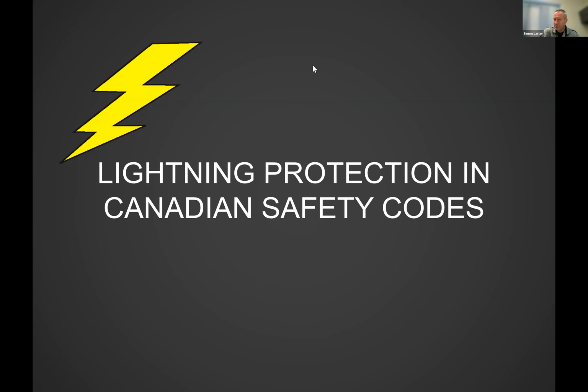The other thing I don't think you will run into very much, though, is from the specific section in B72 on telecommunications equipment protection, and Rogers and Shaw, I think, are both on the CSA B72 committee, and we permit galvanized steel to be used as a grounding conductor in the telecommunications section only. So our main method of stopping theft is concealing the conductor inside a building or in conduit, or even poured into a concrete pour for a reinforced concrete building.